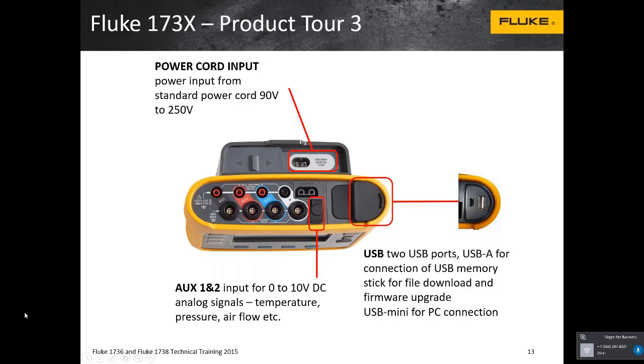Another feature is the auxiliary inputs. This meter has a connection channel where you can hook up an external accessory, allowing you to tie in up to 2 external channels for recording things like pressure or temperature, and you can scale the units manually to make those changes.